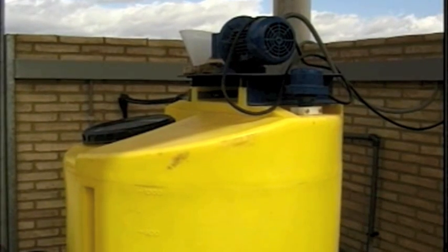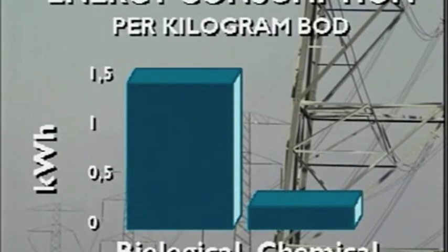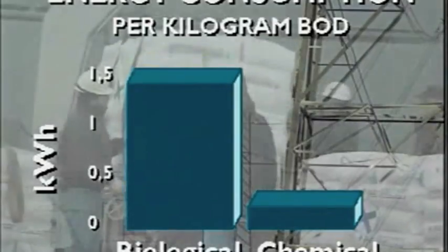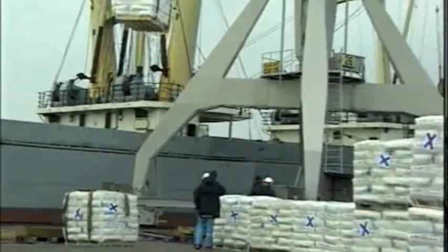Chemical purification requires addition of coagulants, which is done in a small pool and at low energy consumption. The total energy used for chemical treatment is only 15% of that required for biological treatment, even if the energy used for production and the distribution of coagulants is included.